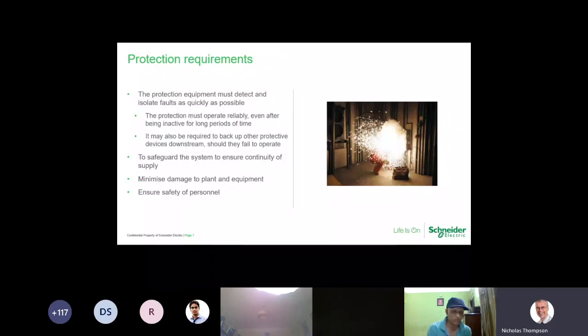And when we start to look at electrical, HV or MV electrical networks, what we don't want is the protection actually operating every week, every day, every month. That would cause significant interruptions to possibly our daily lives. Just taking your own home environment, when was the last time the power went off from your DNO? And they've got a legal responsibility to maintain a relatively good power supply, and they're constantly looking at the protection side of the network, right from 132 kV all the way down to final distribution at 240 volts.